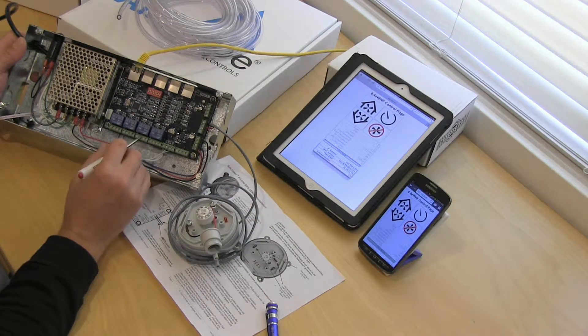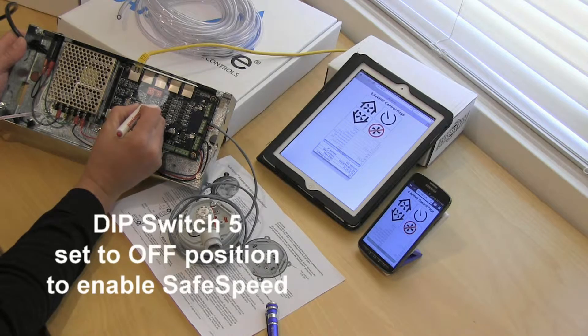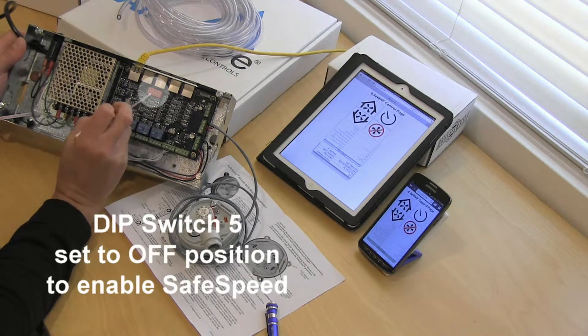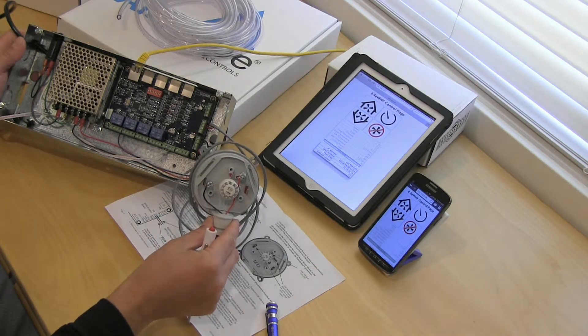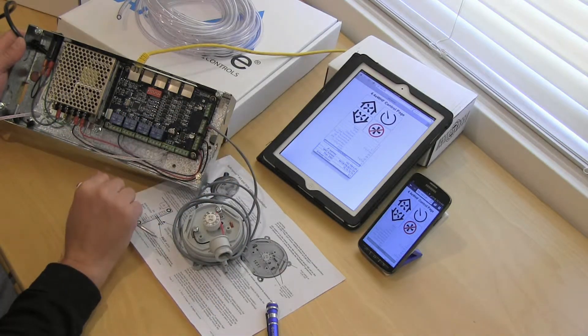Next thing you want to make sure you do is you take dip switch number 5 and you flip it to the down position just like that. So it's got to be in a down position. If it's not, even though you have your sensor hooked up to that control board, it will not be operational.